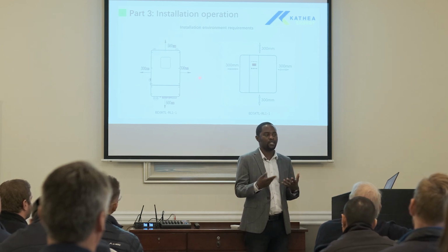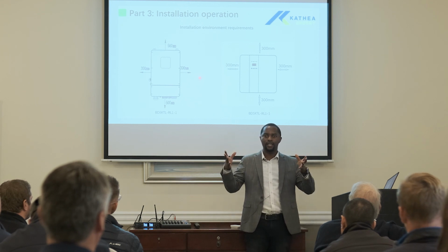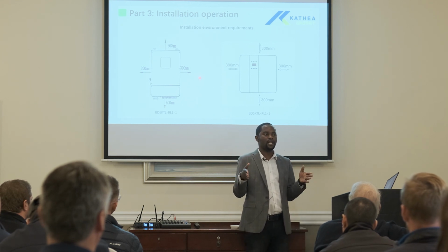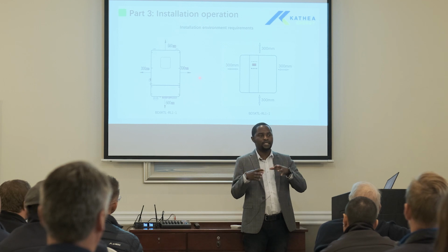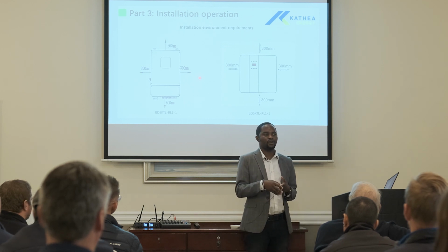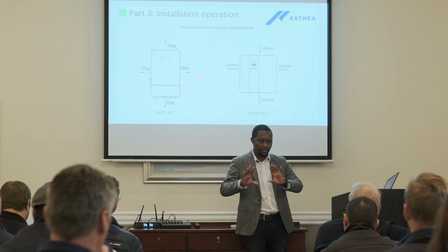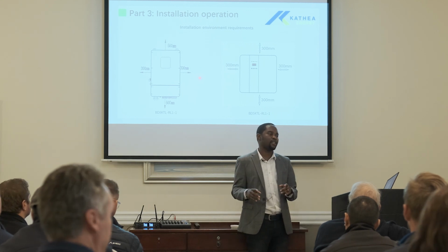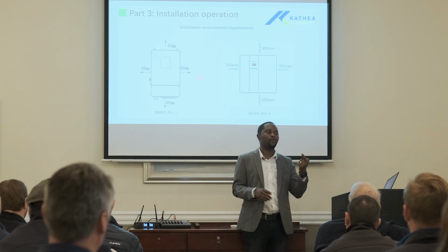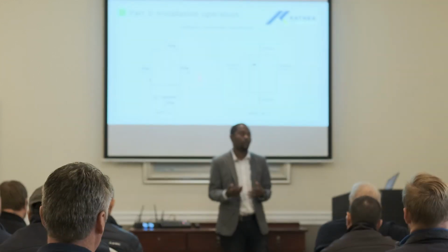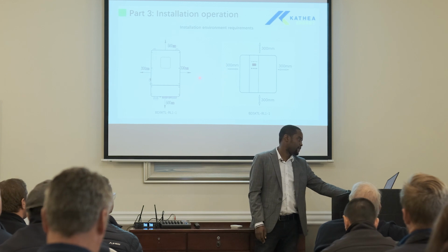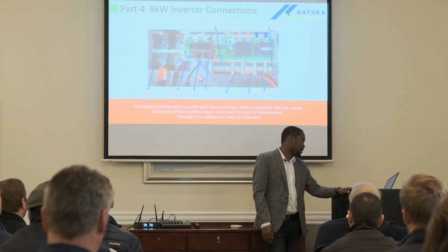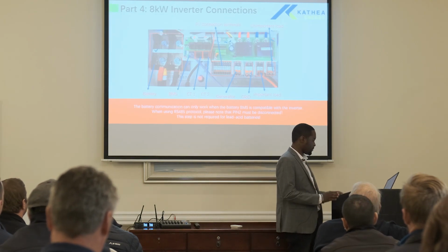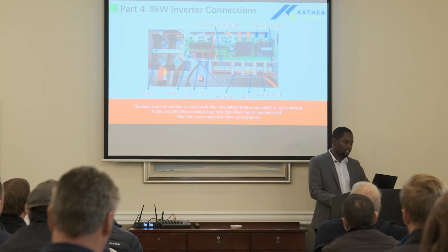So if the heat sink is overwhelmed, let's say you've mounted it in a room where there's no, remember, a heat sink needs at least free air circulation. So if we put it in a basement where there's no free air circulation, then the fans will kick on now. When the inverter is overwhelmed, they will help the heat sinks and cool your inverters further. So underneath, it looks like this. You can tell that it's a bit different from the other inverters that we have in the market.